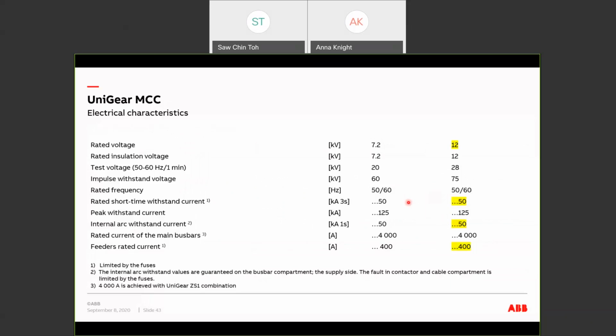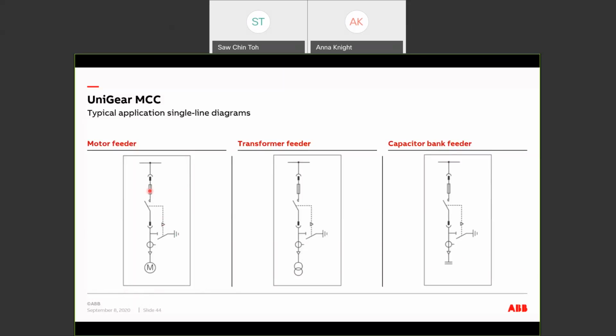The rating of the board is 12 kV, up to 400 amps. This will already cover many of those motor starting requirements, with 50 kA 3 seconds for the short time current withstand, and 50 kA 1 second for the internal arc withstand. The feeders are normally used for direct online starting of a motor, but other than motor starting, we can also use them to switch transformer feeders or capacitor bank feeders.